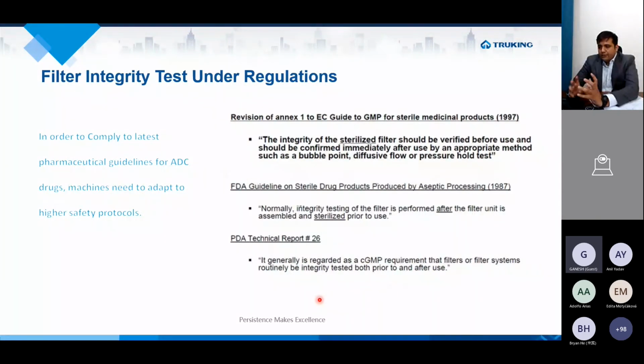And under which regulation it states what steps need to be followed. So in order to comply with the latest pharmaceutical guidelines for ADC drugs, the machine needs to be adapted to higher safety protocols. As per the EC Guide to GMP for Sterile Medicinal Products 1997 edition, it clearly states that the integrity of the sterilized filter should be verified before use and should be confirmed immediately after use by an appropriate method, such as bubble point, diffusive flow, or pressure hold test.